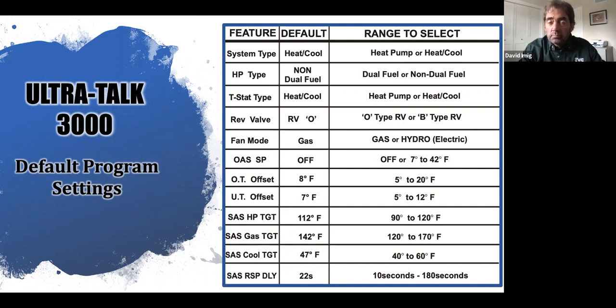Reversing valve. Then I have fan mode. Is my fan energized immediately upon a heat call, or is there a time delay? Gas, of course, is going to give you the normal time delay. Hydro, hot water, or electric is going to give you immediate fan. Outdoor air sensor, am I using it? If not, and I come out in the box with it set to off, if I'm using it, I must go to that and select a temperature between 7 and 42 degrees that I'm going to bring on auxiliary.